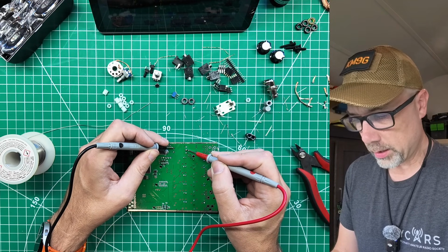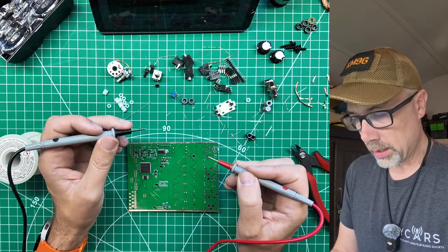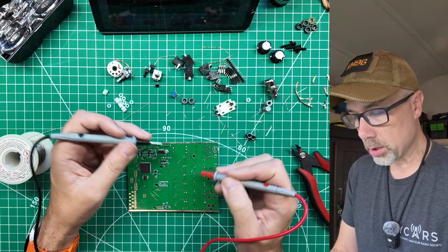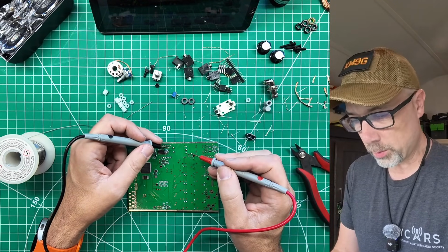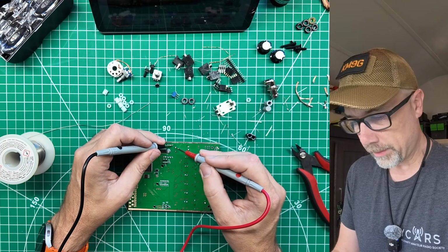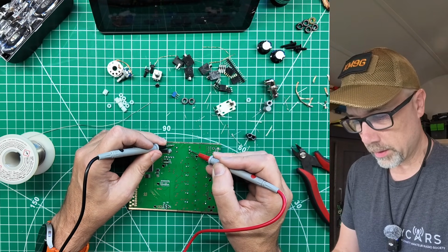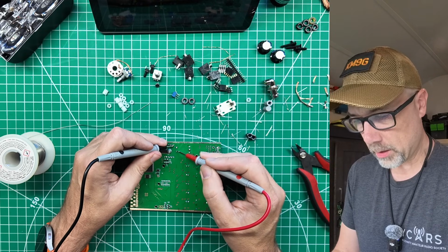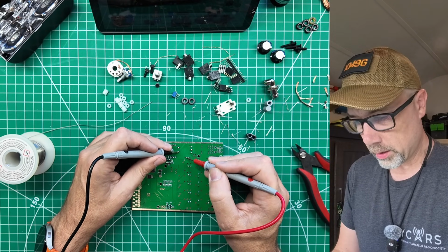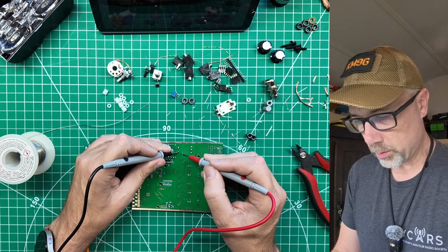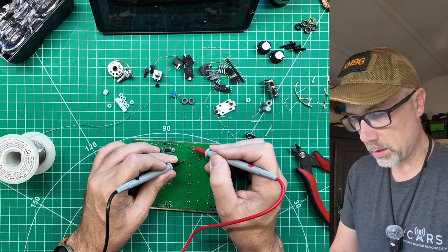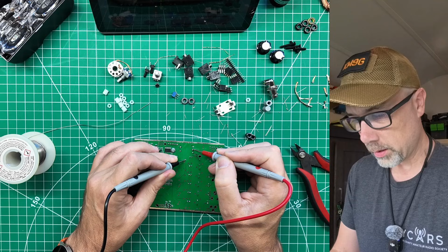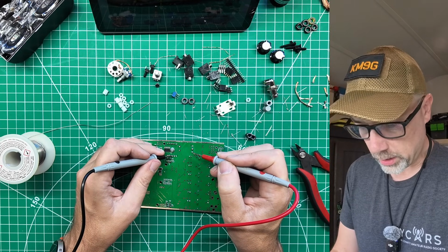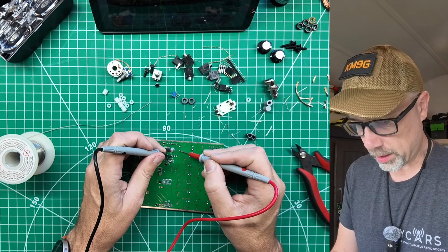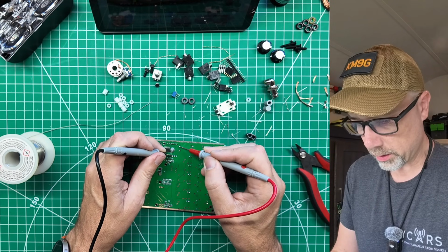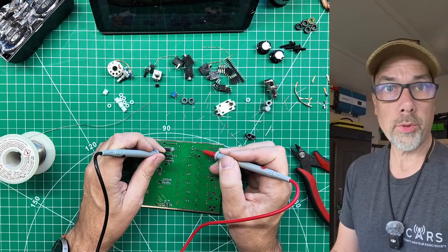That's good, that's good, that's good. Now you can also probe continuity between all of those points, the 3 transformer leads and then the 3 test points. So there, there, there, and then this one, it would be, and then this test point here, there, and then number 3 of your final transformers, there. See what I mean about not getting a good test right away? There, and there. So that's all 3 of those.